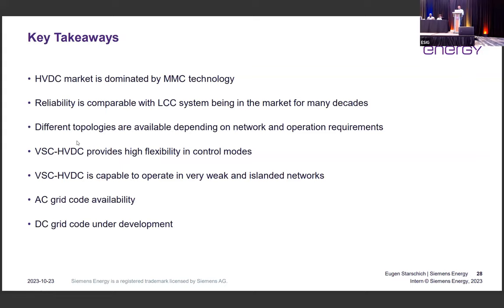Coming to the end, what are the key takeaways? The HVDC market is now dominated by modular multi-level converter technology. The reliability is comparable with LCC systems, which have been on the market for many decades, but MMC technology has already caught up with this availability. Different topologies are available, highly depending on the network operation requirements. There is a full scale of different options, and it is up to the operators to define which one to take. The VSC HVDC provides high flexibility in control modes, which should be utilized by the network.